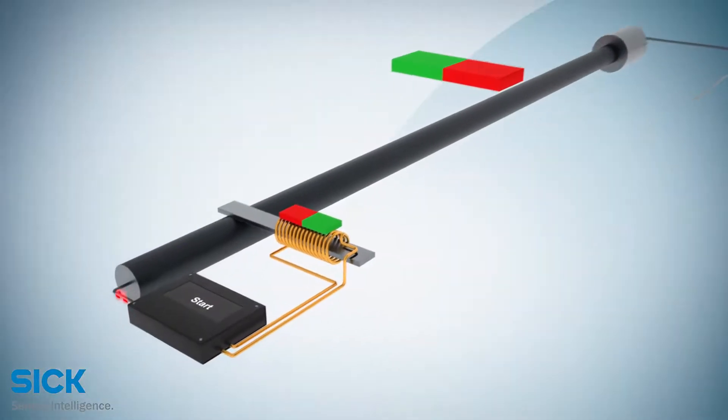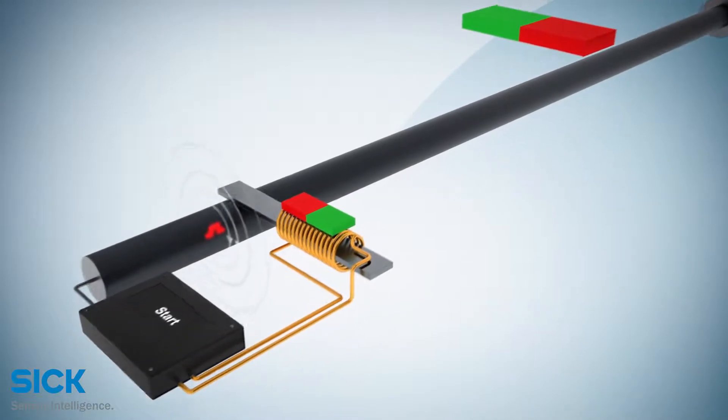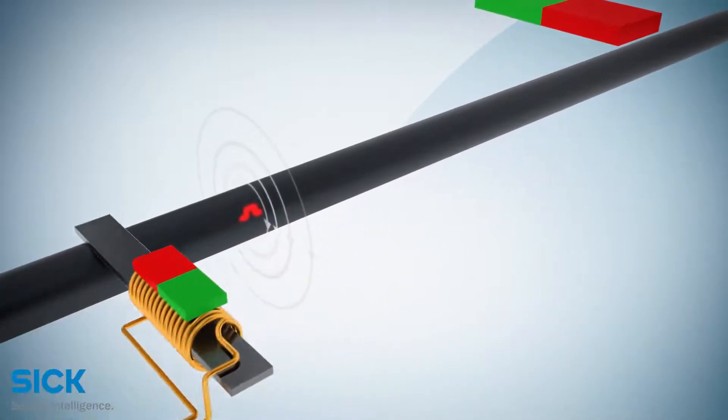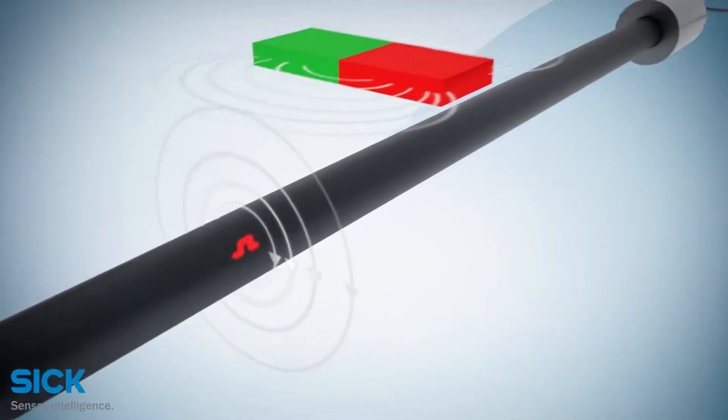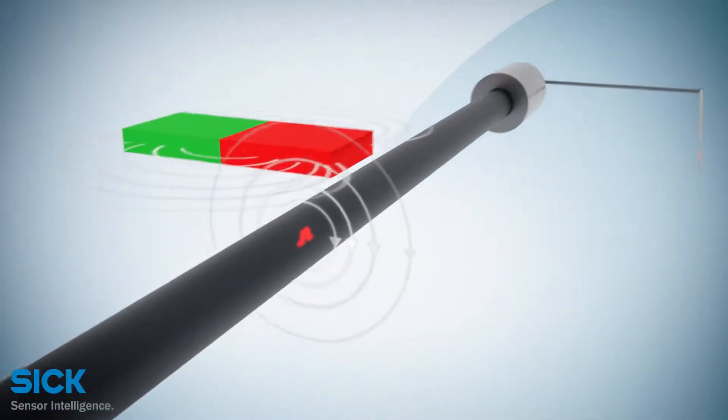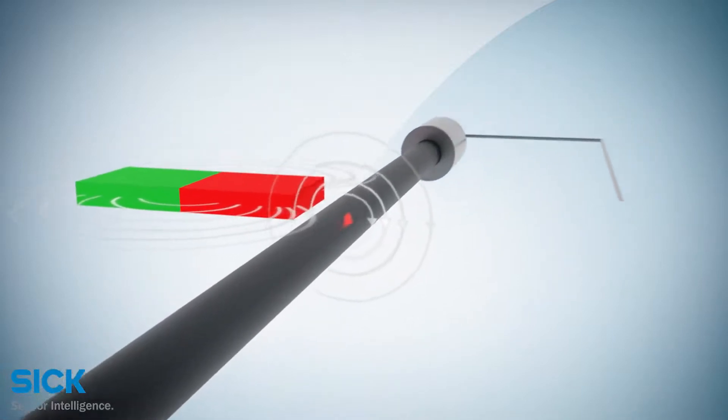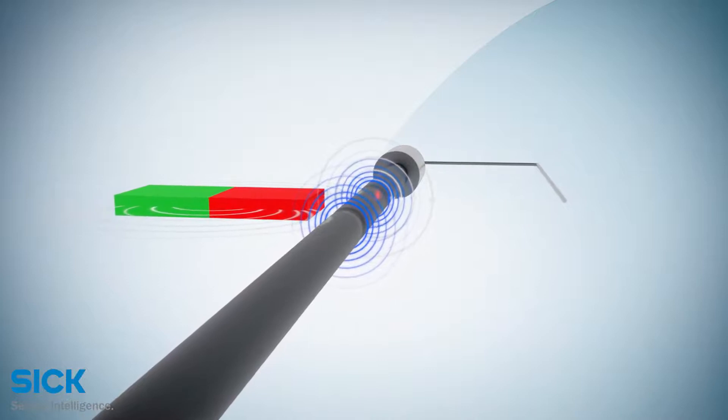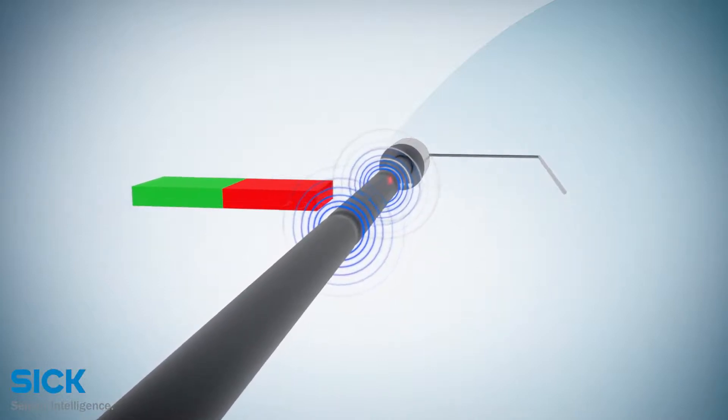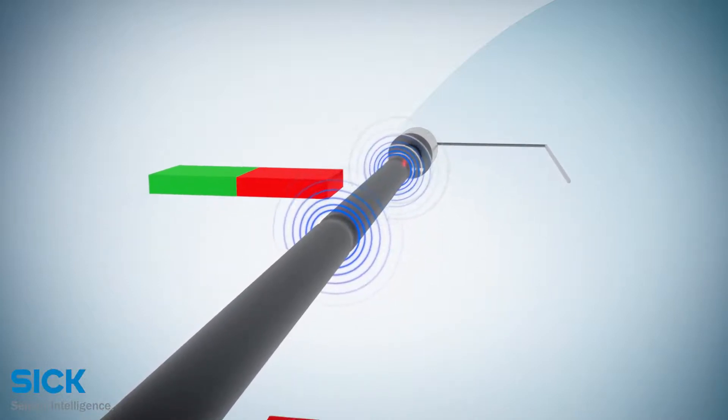A short current pulse is applied to the waveguide and creates a radial magnetic field. The position magnet, which is connected to the movable machine part, generates a magnetic field at its location on the waveguide. The momentary interaction of the magnetic fields causes a torsional strain pulse that propagates the length of the waveguide in both directions.